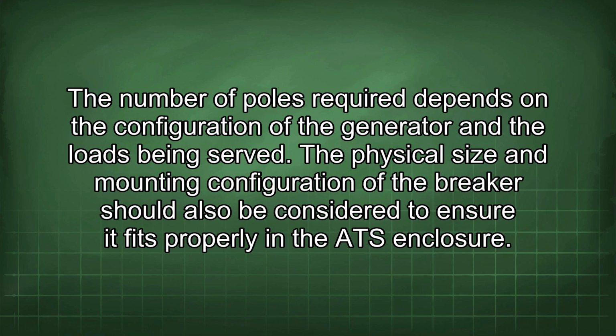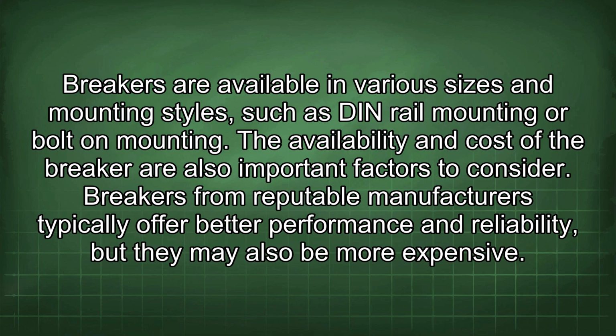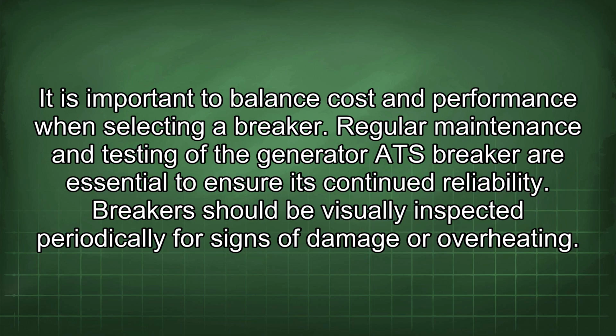The physical size and mounting configuration of the breaker should also be considered to ensure it fits properly in the ATS enclosure. Breakers are available in various sizes and mounting styles such as DIN rail mounting or bolt-on mounting. The availability and cost of the breaker are also important factors to consider. Breakers from reputable manufacturers typically offer better performance and reliability, but they may also be more expensive. It is important to balance cost and performance when selecting a breaker.